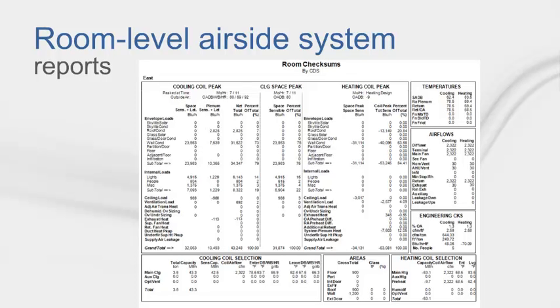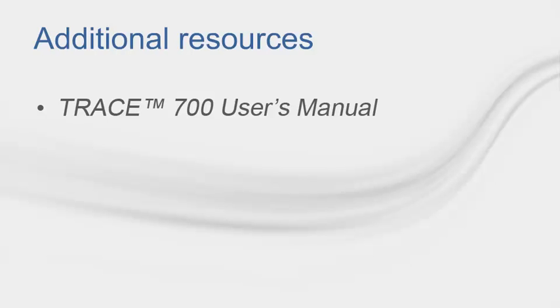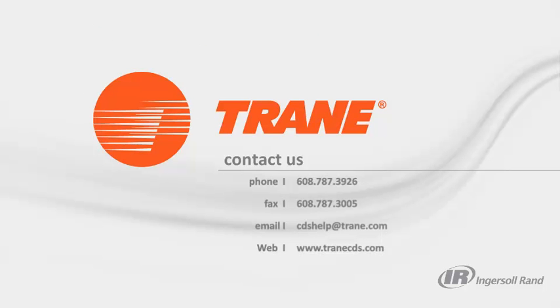To finish up, after calculations have been completed, you would want to look at the system component selection report or room checksums for all coil and fan sizing information. Also note, some of the numbers in the zone checksums may not equal the straight addition of the same numbers in the room checksums, because the room checksums report shows each room at its individual peak time, not a zone peak time. This video has covered why zoning is important and how to do it properly for all levels of air side systems. For more information, you can check out the TRACE User's Manual, page 325, or in the program with F1 help. Thanks for watching. Have a nice day.